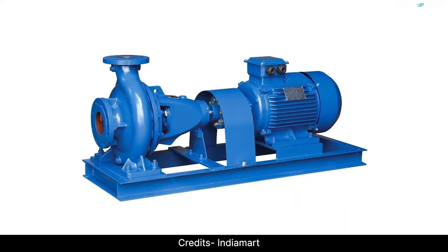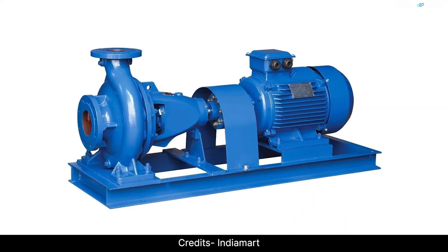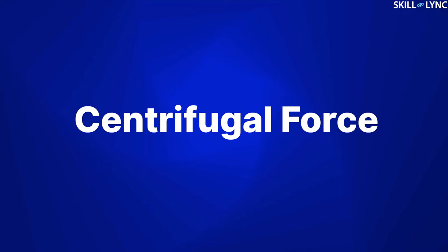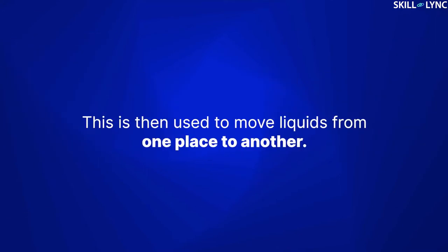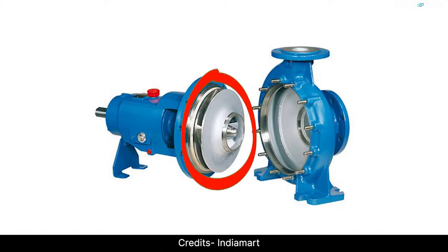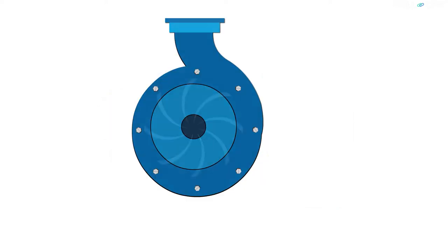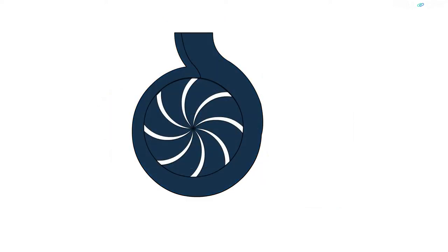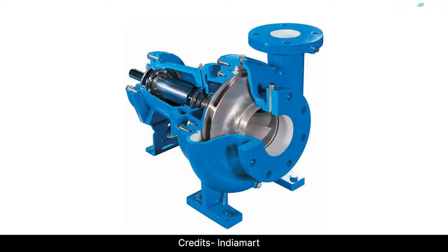In this video, we will be talking about a very specific type of pump called the centrifugal pump. A centrifugal pump uses centrifugal force to generate a pressure difference, which is then used to move liquids from one place to another. The centrifugal force required to move the liquids is generated by a component called an impeller. The impeller consists of radial vanes which extend into the impeller body.